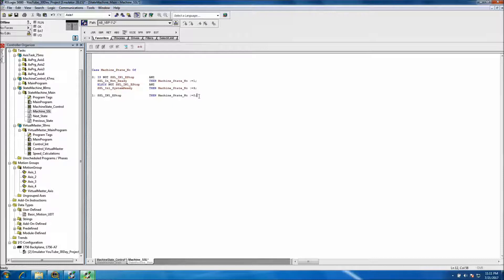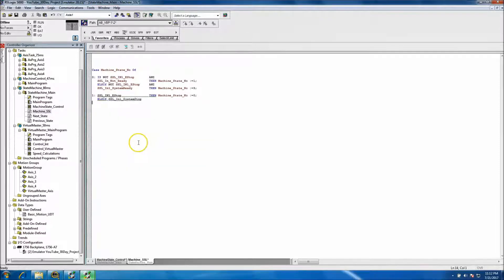Plug the numbers in and then ELSE IF. We want to say: if not stopped and the system is ready, then go to State 3. We'll pull our not-stop tag — I believe that's an SSL — system stop. And we'll say NOT, so it's kind of spread out.